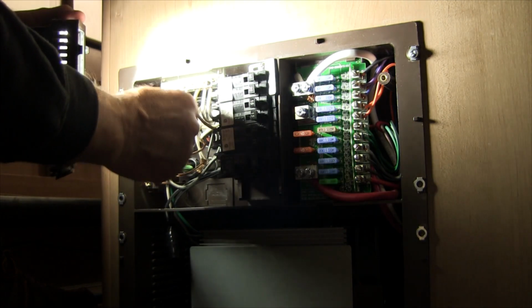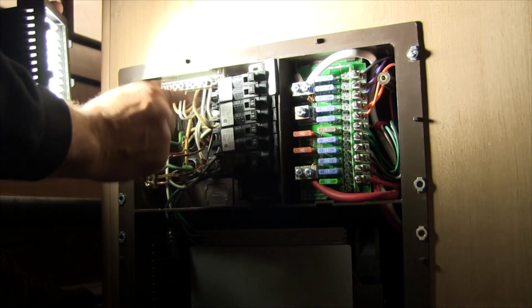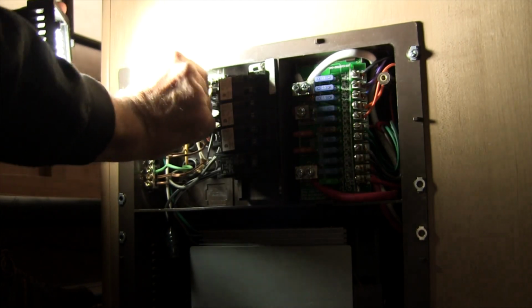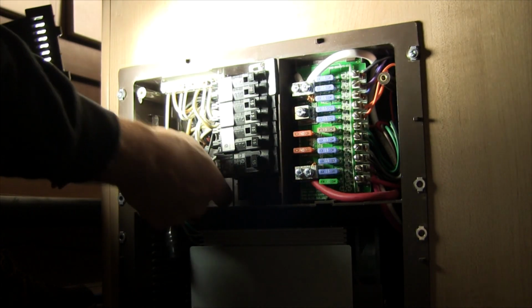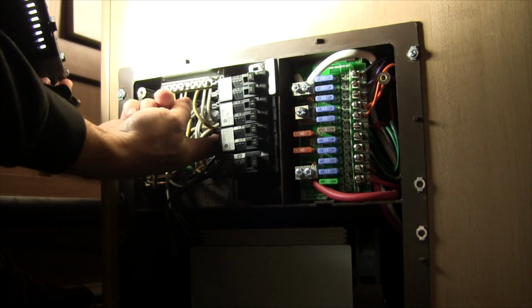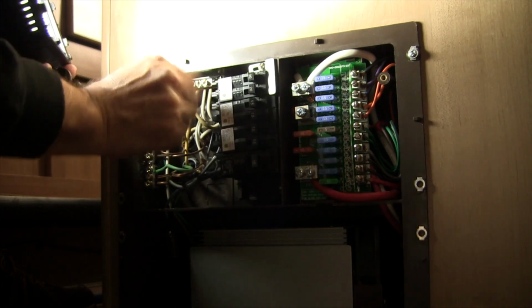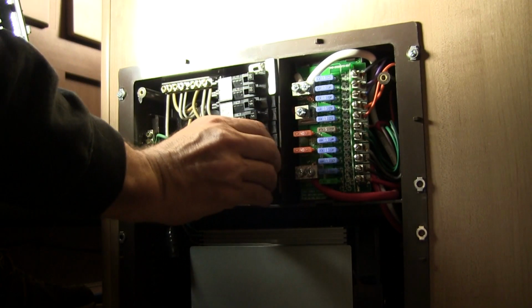We look at another bar inside here, the neutral bus. There are yellow wires, some white, nothing looks burnt. Do the same for the wires at the bottom of the circuit breakers; none of them should be loose or look burned. Be sure to check that the breakers are solid in there, tight.